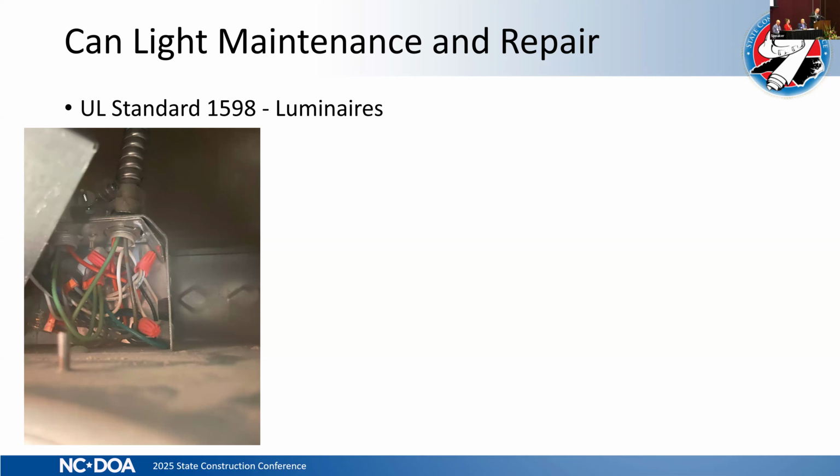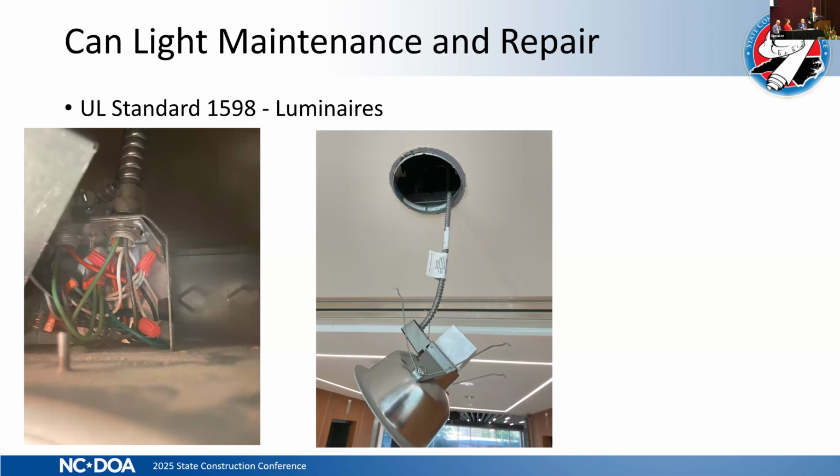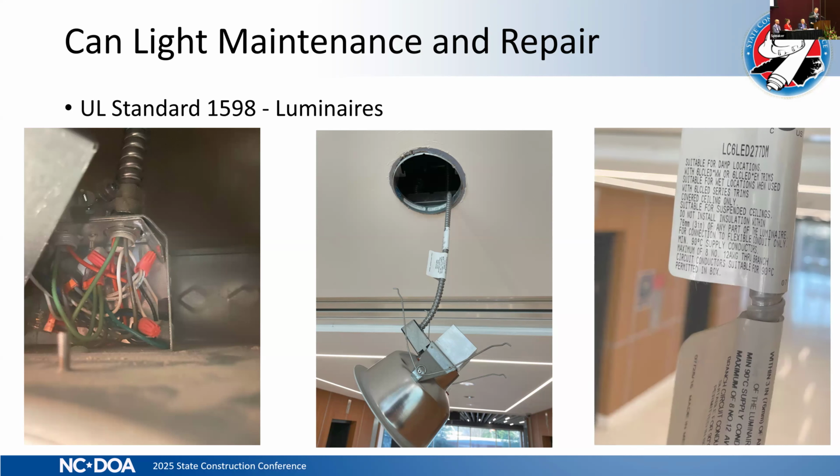That's problematic. So I went to UL and I asked Jeff Fecto, who I specifically went and asked, please explain to me how we got this fixture that has a UL listing. And Jeff's comment was, well, there's a tag on it. What does it say? It says it's for suspended ceilings. Is that hard ceiling a suspended ceiling? Well, I asked the contractor that.